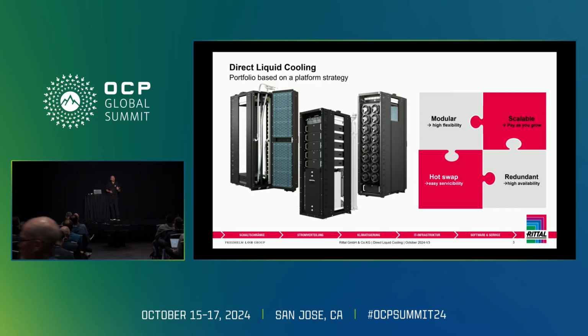In response to all of that, Rittal has developed a platform portfolio of direct liquid cooling, based on a platform strategy. Number one, it's modular, making it highly flexible. We can start anything from 30 kilowatts, all the way through to 100, 150 kilowatts, and then into a single rack solution, 1 megawatt and beyond.